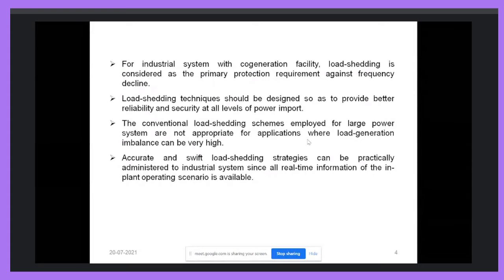To maintain the load and generation balance, they have to use the load shedding technique. The load shedding technique should be designed to provide better reliability and security at all levels of power import. At all levels of power import means, suppose the industrial plant has its own generation, but that generation is not sufficient to supply the connected load. In this condition, they have to draw power from the utility grid. The frequency deviation depends on the mismatch amount, that is, the difference between generation and connected load. The frequency stability depends on that.